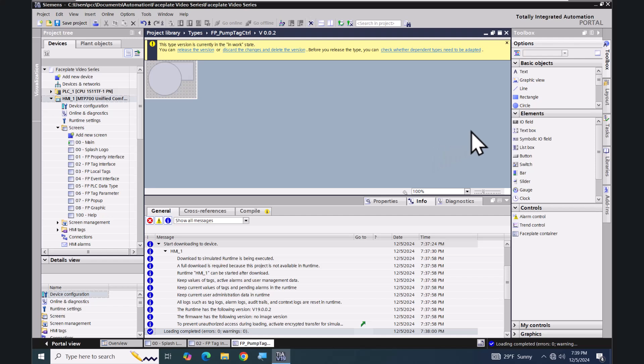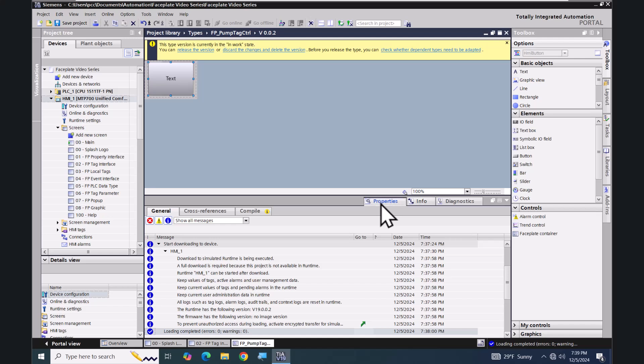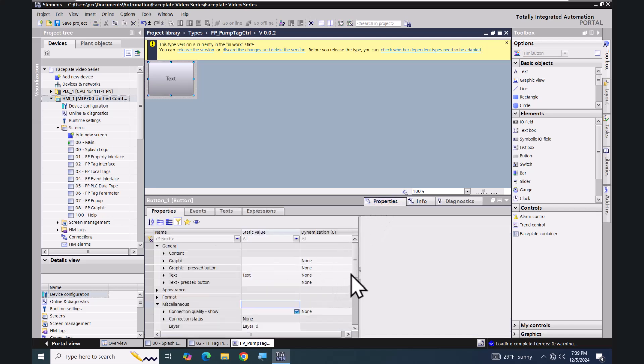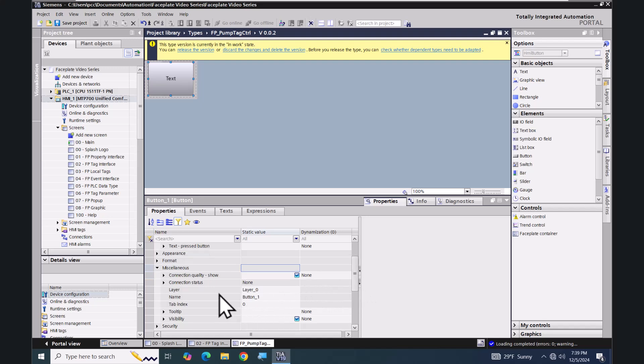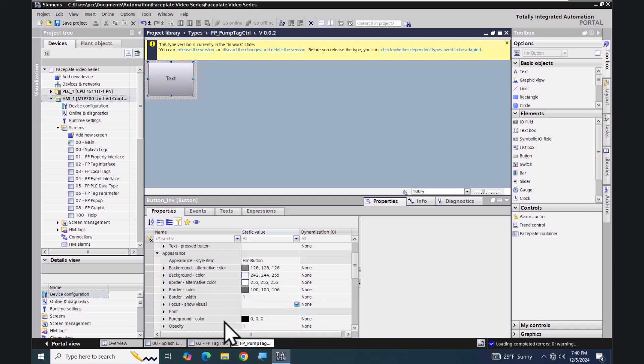I'd like to drag a button object onto the screen so that it covers up my pump. In the button's properties, I'll go to the Miscellaneous area and change the layer — instead of layer zero, I want to put the button on layer one inside the faceplate. I'll also change the button's name to 'button_INV' for invisible.